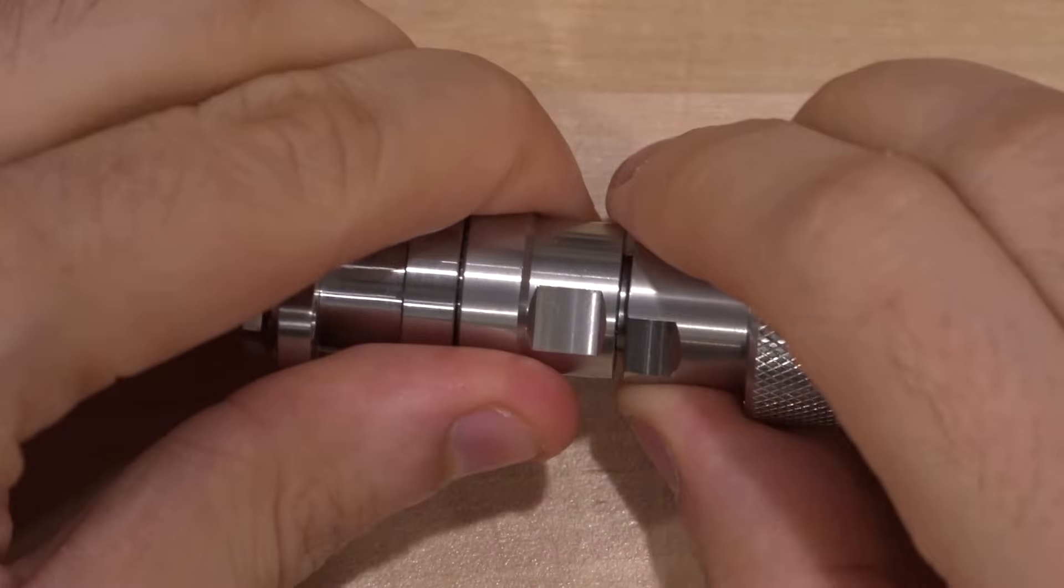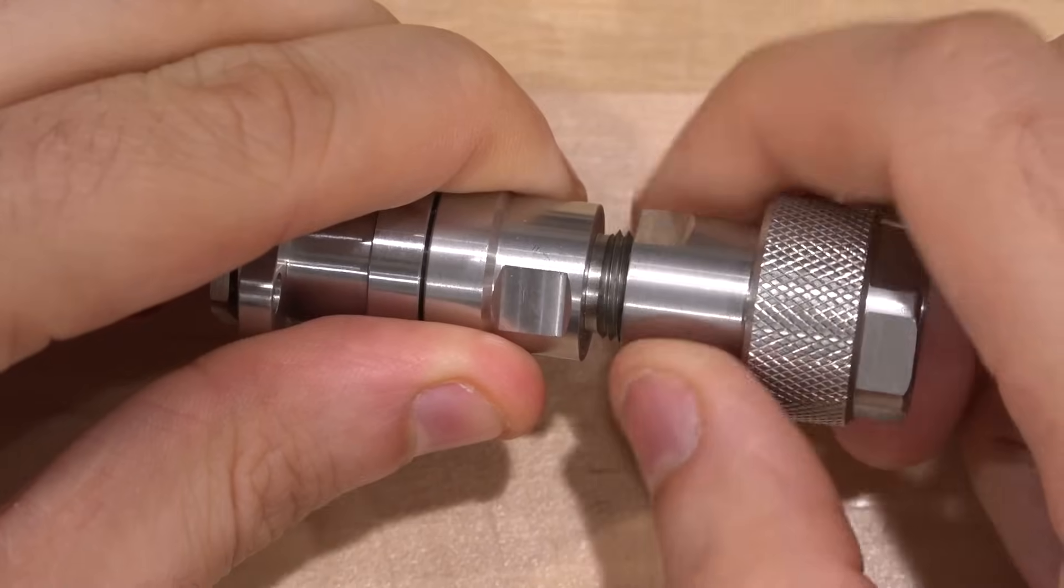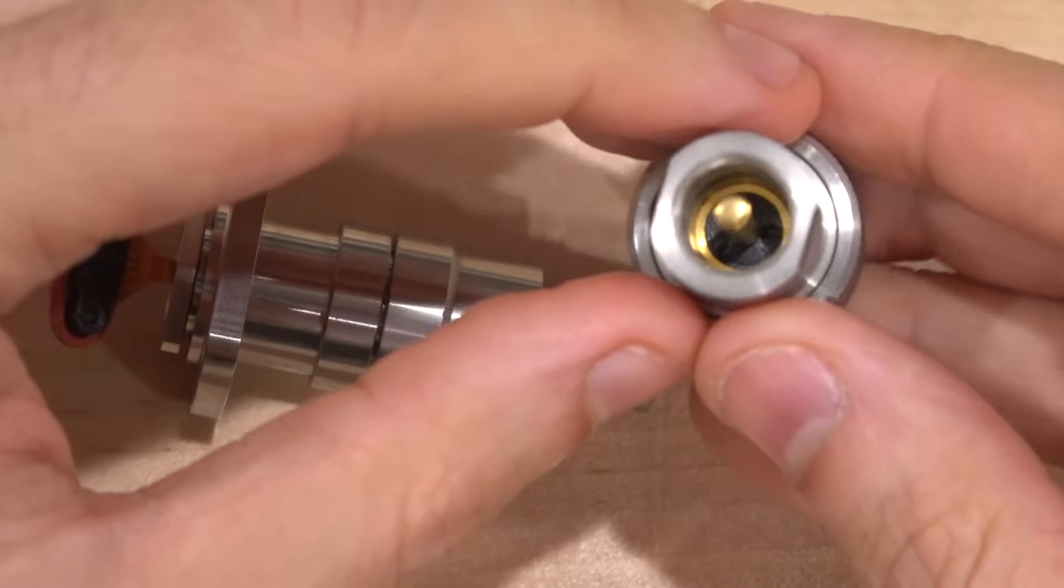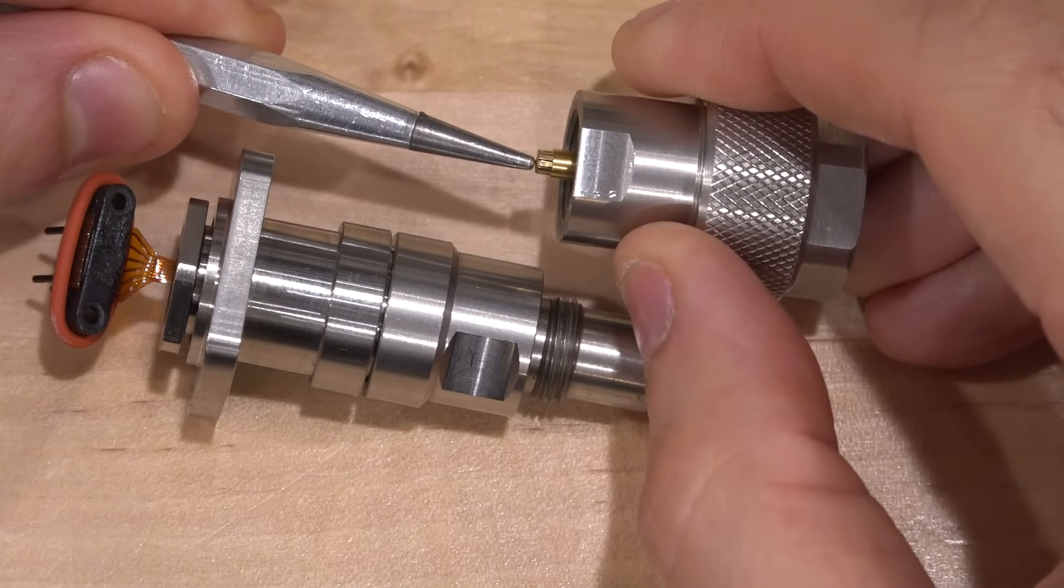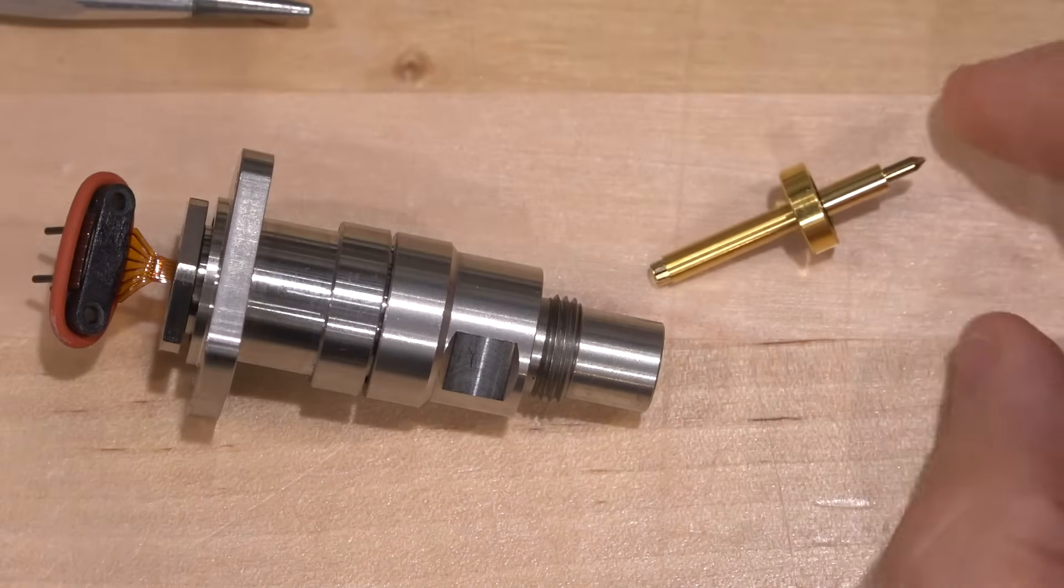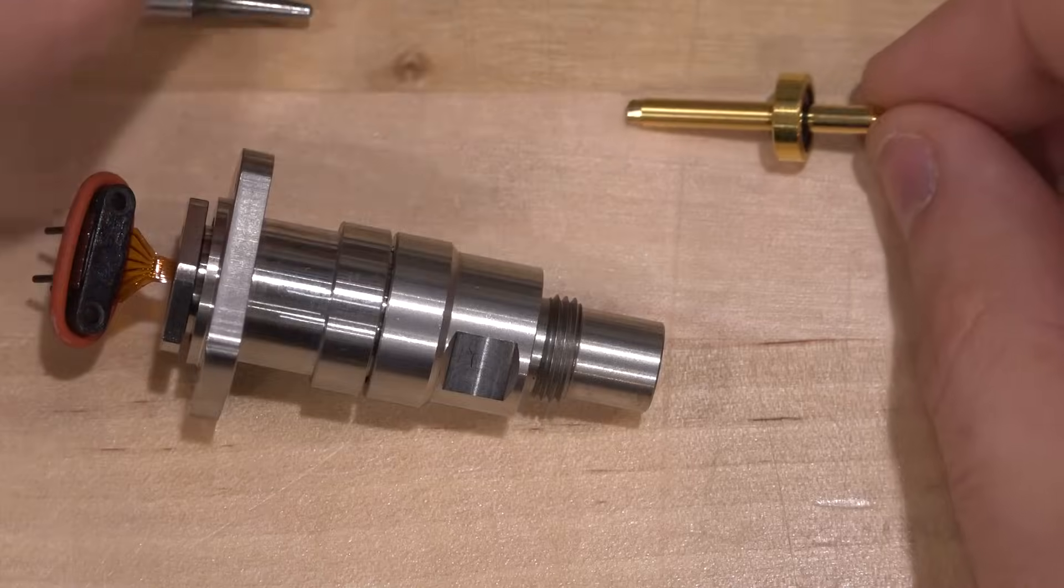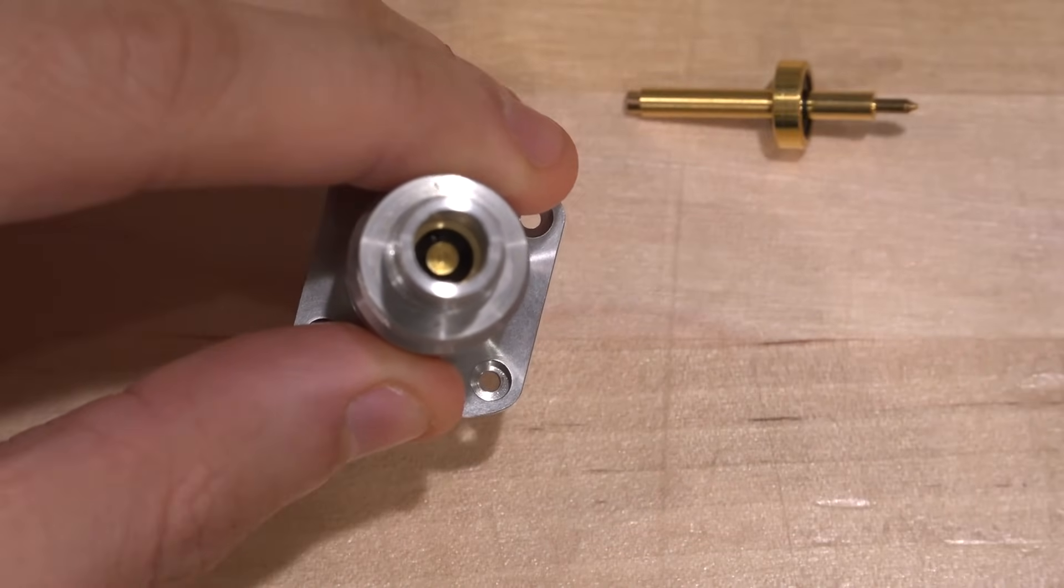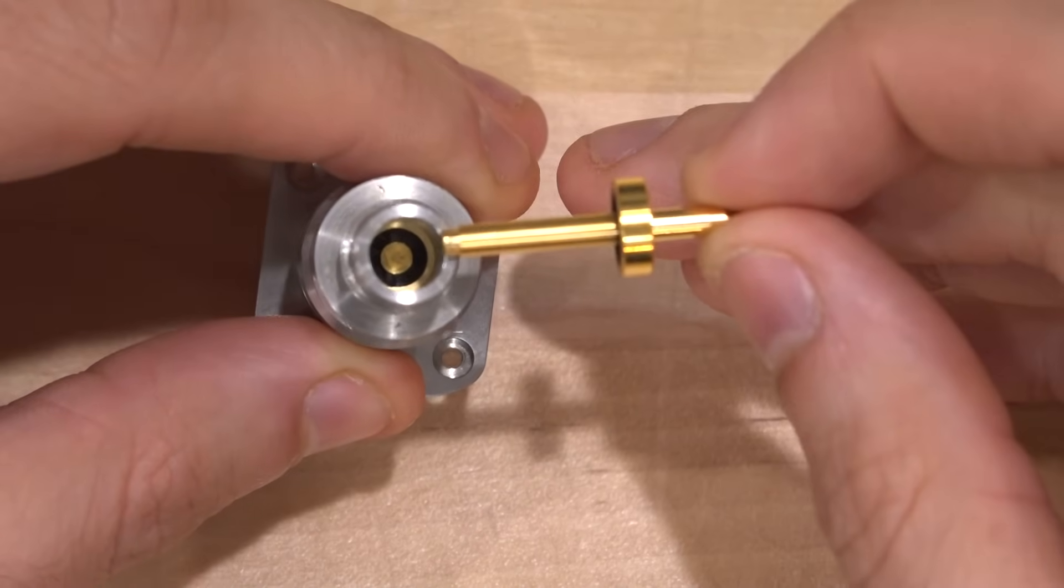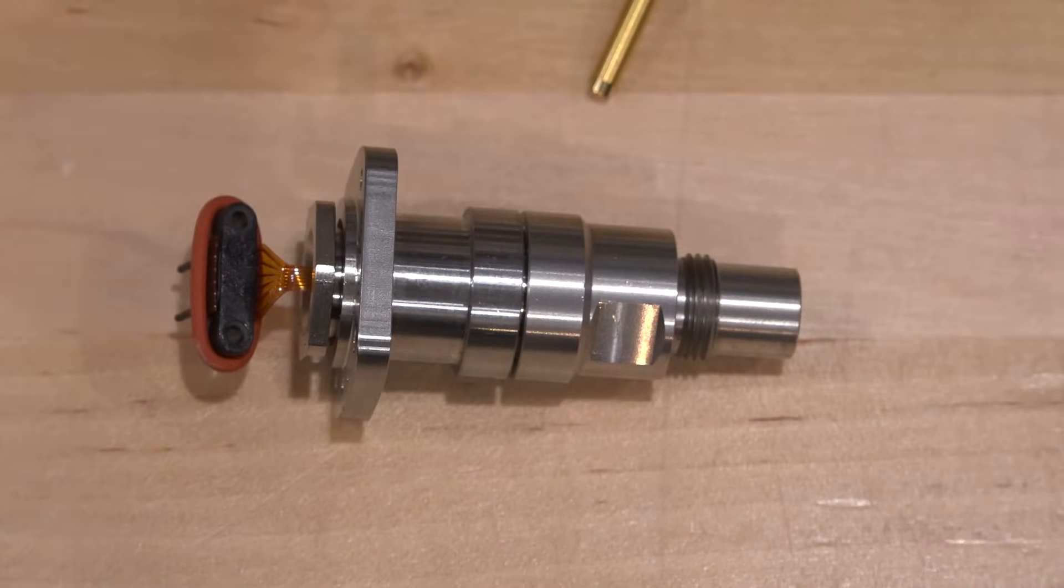I loosened these interfaces, so we should be able to separate this. Normally you never take this part apart because you don't want to damage the connector and its alignments. But we can see how it's made. There we go. Here's the center pin. The center pin does have this part that makes contact, it's somewhat springy. So this part maintains our nice 50 ohm interface. These are all machined high precision components. At the end, we have the contact. This is how they managed to get some degree of freedom, the compression of this pin against that gold plate you see at the bottom.